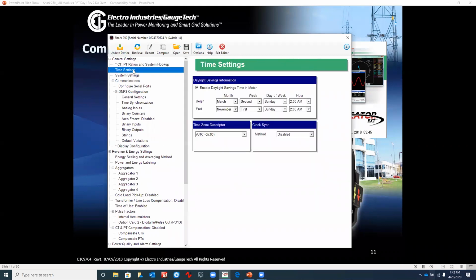Okay, and then let's go down to the time settings. We use the time settings to set up for standard time or daylight savings, the zone descriptor, what area of the world you're located in where you need to set your reference time, and the clock synchronization method. In this case, it's set for disabled, but this meter offers a line sync and NTP option, which is great if you have an NTP clock that you can sync to, which has a satellite GPS connection. You would want to use that. That's the best option that you have to sync the time with this meter.